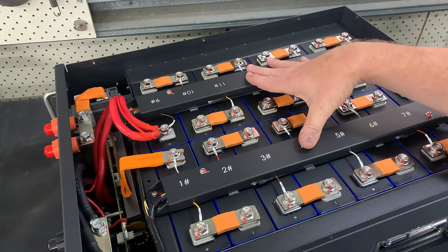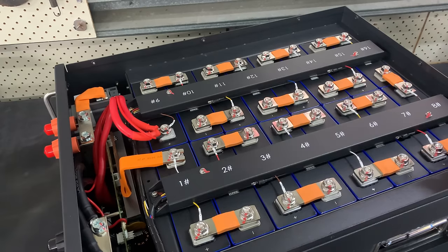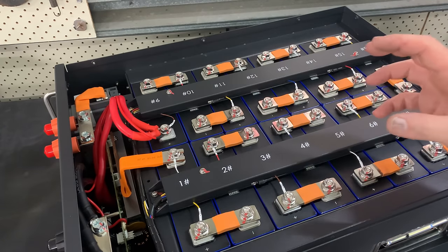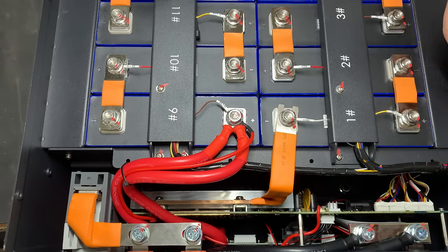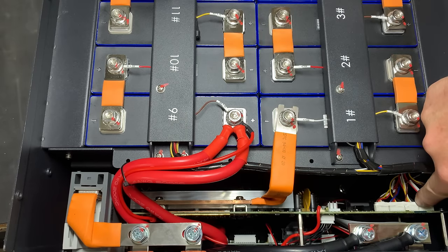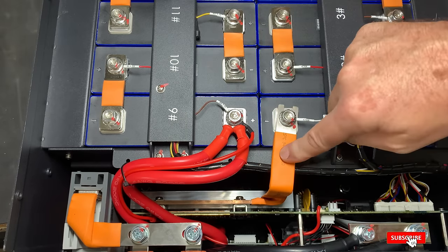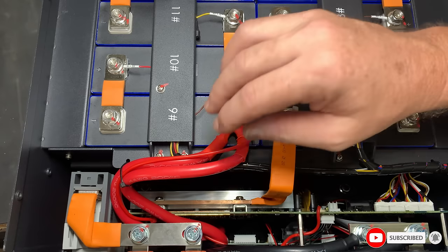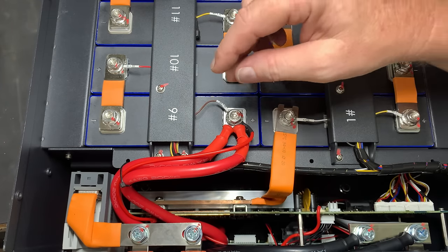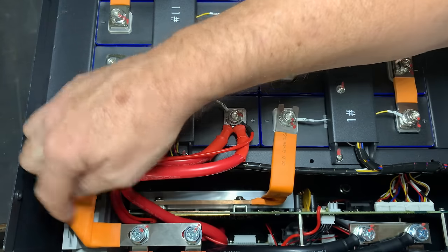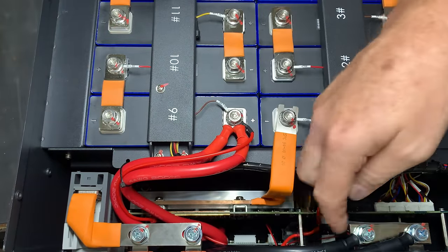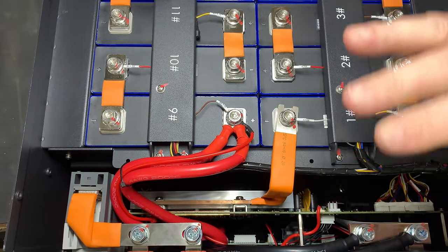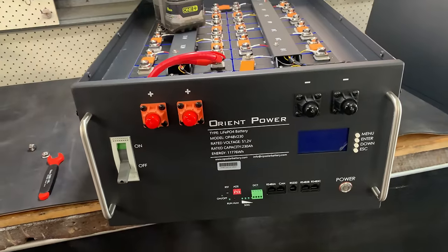The battery looks very well laid out. We've got numbering of all the cells, we have witness marks or a little pen on each of the cells for where they've been torqued down so we can see if anything has moved in shipping. I really like seeing that. We've got four temperature sensors evenly distributed at the top of the battery pack. There's fish paper between all cells. We've got the two big bits of steel across the top which hold the cells in place and are very easily removed by two screws at each end. Looking down on the battery management system we can see the BMS leads come in and attach to the motherboard. We've got the negative on a solid bus bar and on the positive side we've got dual four gauge wire coming into the battery going into the breaker.